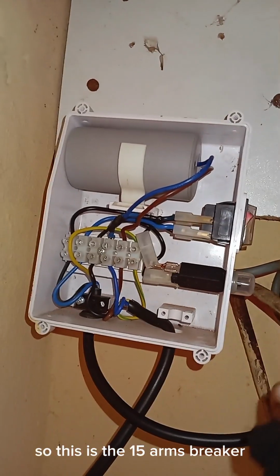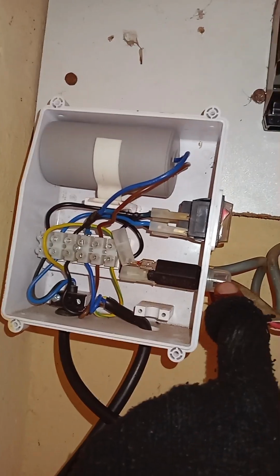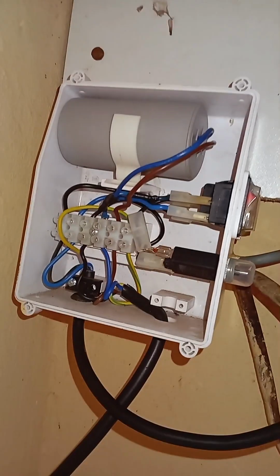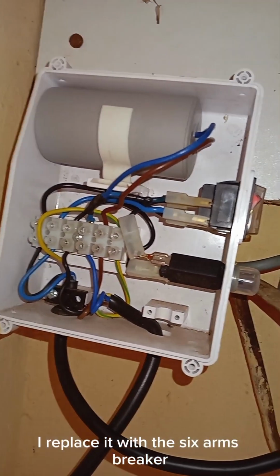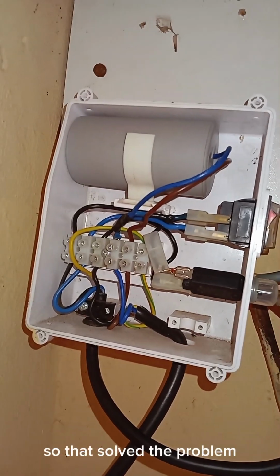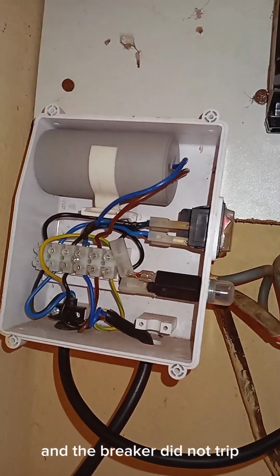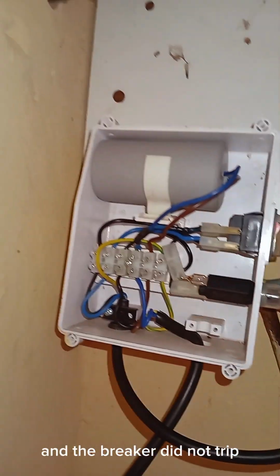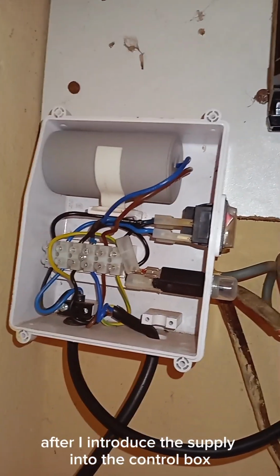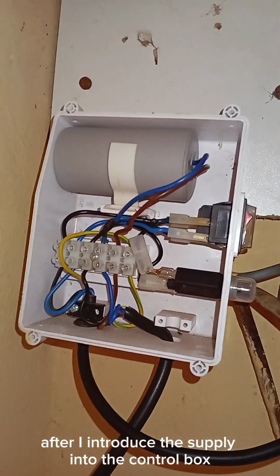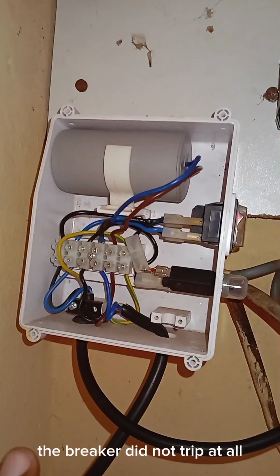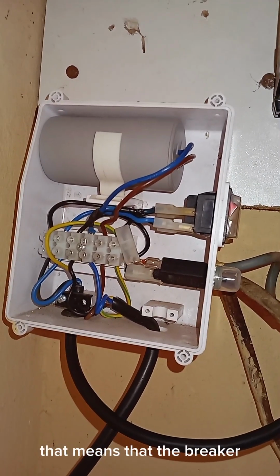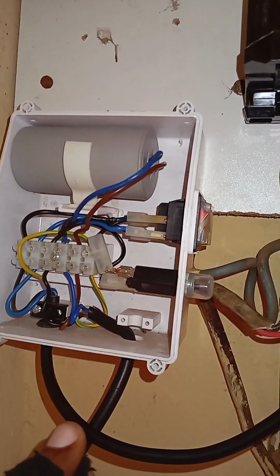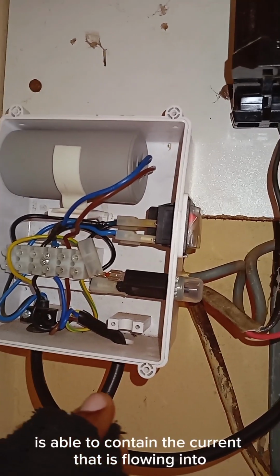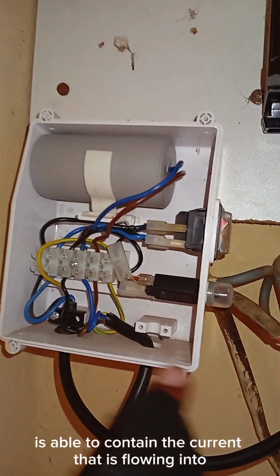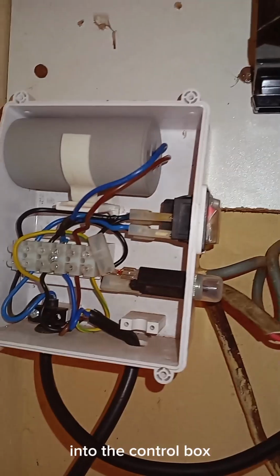So this is the 15 amps breaker, this one here. The moment I replaced the 6 amps breaker with it, that solved the problem, and the breaker did not trip after I introduced supply into the control box. The breaker did not trip at all. That means that the breaker is able to contain the current that is flowing into the control box.